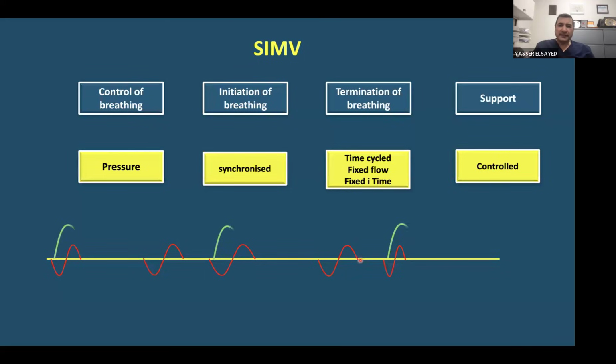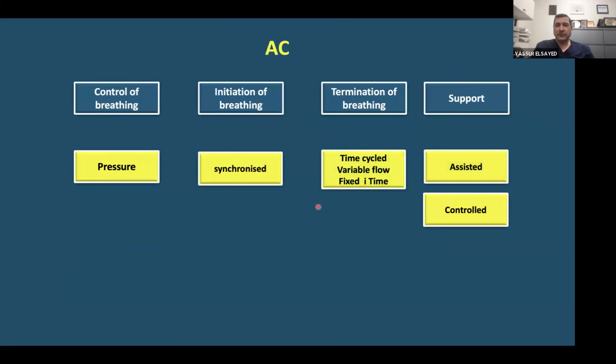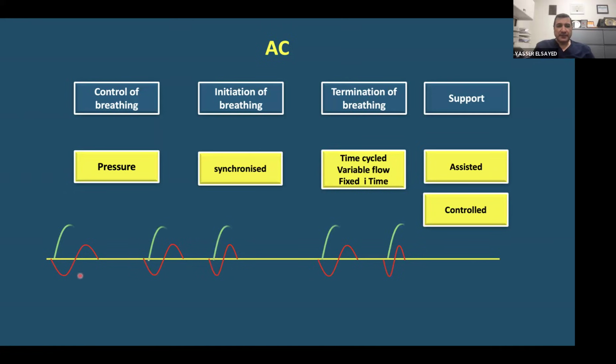Now, you can notice that only the number of breaths that I decide on the machine are supported, but if the infant breathes in between, those breaths are unsupported. So if I apply a rate of 25 on the machine, but the patient is taking 50, only 25 are supported and 25 are unsupported, which is different from AC, assisted control. It is controlled, assisted by the patient, meaning that every single breath by the patient is assisted. So there is nothing in between.